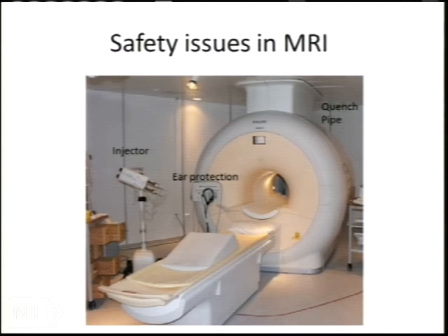Very important for that quench pipe to work when it's needed. I've only seen it happen a couple times, one purposely and one not purposely, but it's very dramatic when it happens. Things happen very, very quickly. So the other thing I put on this diagram about safety is ear protection, because this thing is very loud.